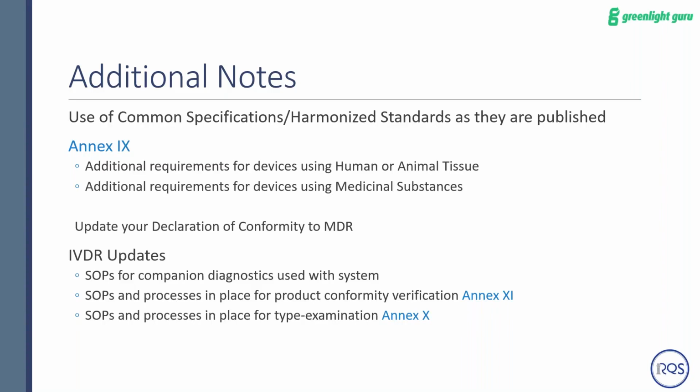Some general updates: separate SOPs for companion diagnostics and how they are used with the system and how they are tested, SOPs and processes in place for product conformity and verification, and then SOPs and processes for type examination as well. Definitely, if you are an IVD manufacturer or somebody within that scope, or an economic operator for IVDs, make sure you are reviewing that one in detail. We've got some experience with that, so you can reach out to us if you have questions on the IVDR stuff.